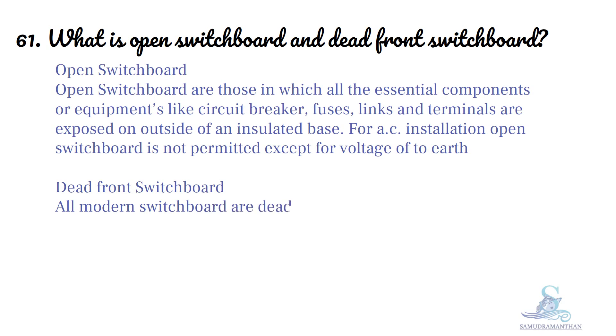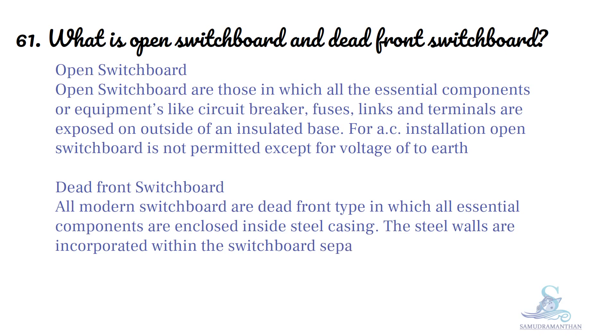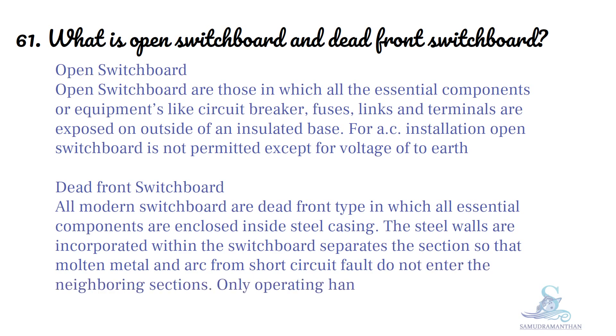Dead front switchboard: all modern switchboards are dead front type, in which all essential components are enclosed inside a steel casing. The steel walls incorporated within the switchboard separate the sections so that molten metal and arc from short circuit faults do not enter the neighboring sections. Only operating handles and indicator lamps are exposed outside.